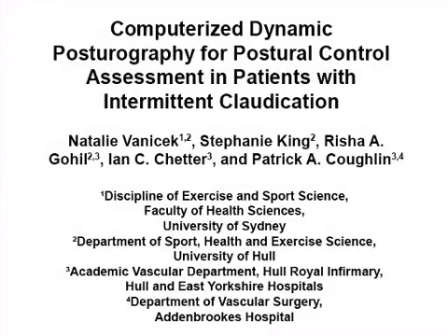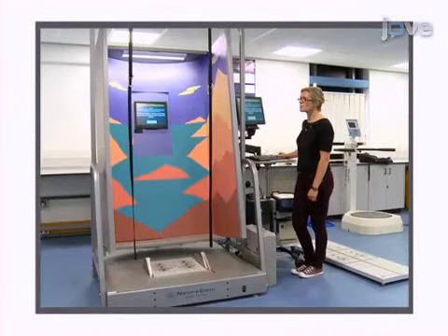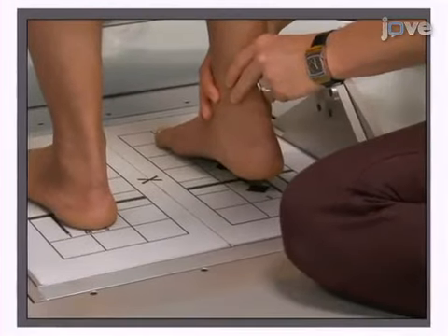The overall goal of this procedure is to assess a patient's balance objectively with the use of computerized dynamic posturography through 2 diagnostic tests. This is accomplished by first ensuring the dual force plate support surface and visual surround are calibrated.